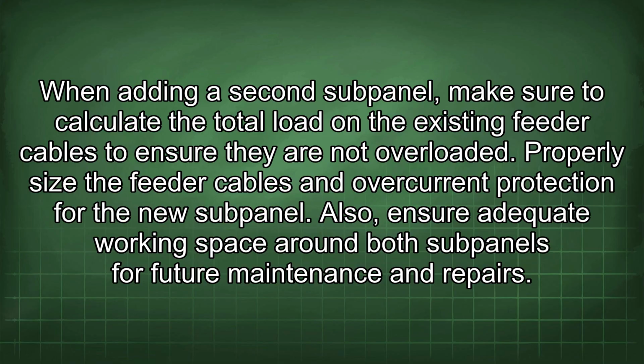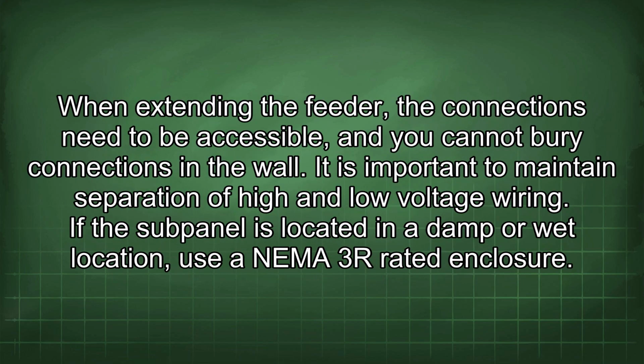Also, ensure adequate working space around both subpanels for future maintenance and repairs. When extending the feeder, the connections need to be accessible, and you cannot bury connections in the wall. It is important to maintain separation of high and low voltage wiring. If the subpanel is located in a damp or wet location, use a NEMA 3R rated enclosure.